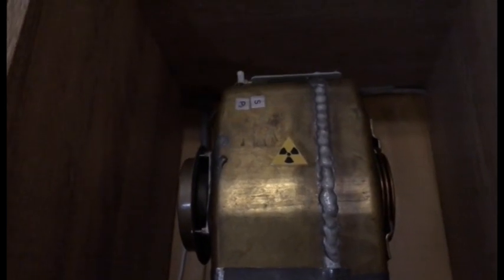Now let's dig into more of the technical side of it. This is the X-ray head at the top. That's what produces the actual X-rays themselves. It's a fully contained unit. It has the filament transformer, high voltage transformer, and the X-ray tube built into one unit.